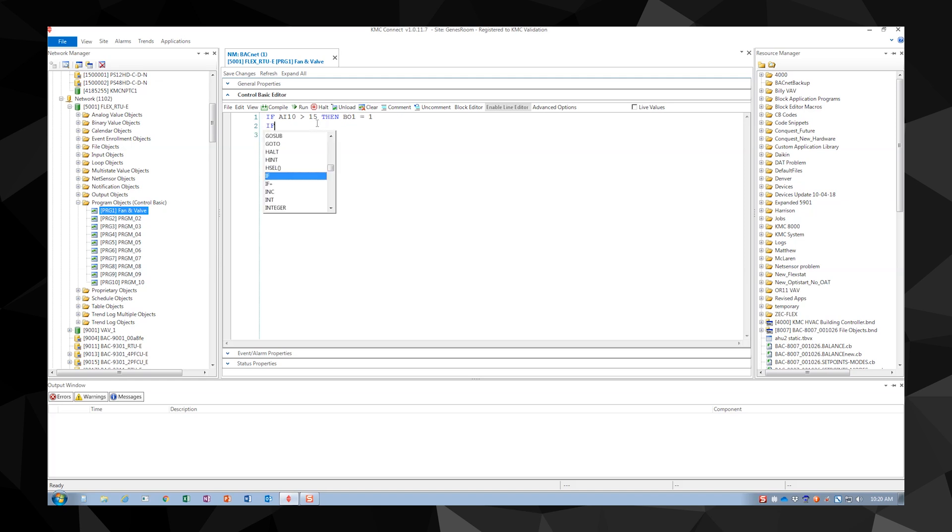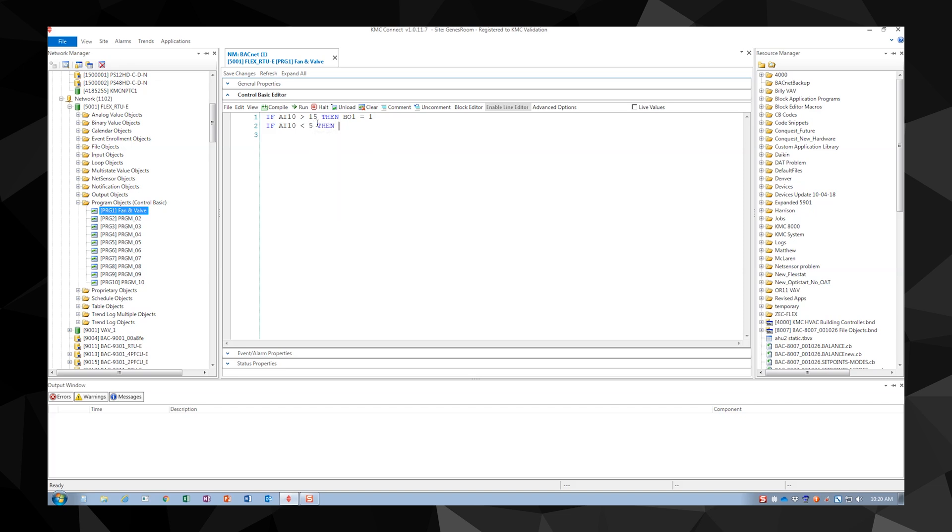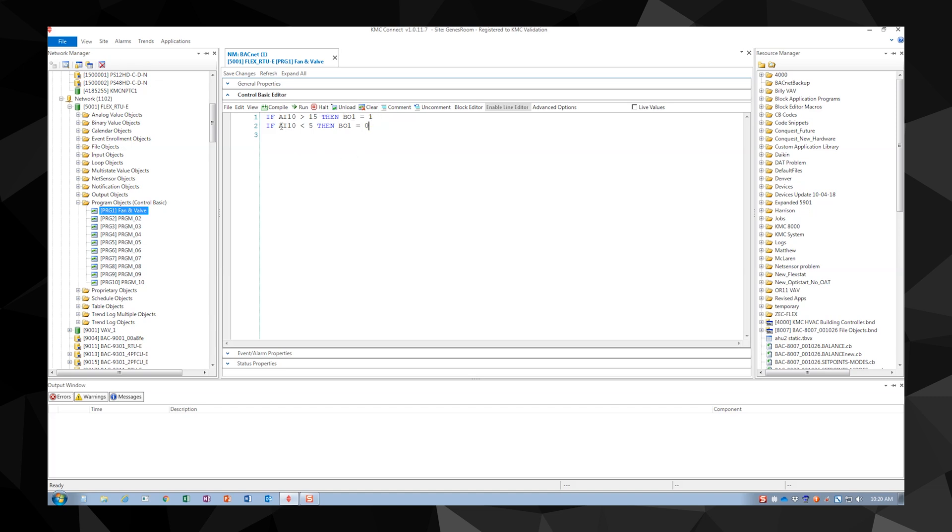Our second line of code will read if analog input 10 is less than 5 then binary output 1 equals 0. These two lines of code work together. If analog input 10 is greater than 15, binary output 1 will be set to 1 or it will be started. Once analog input 10 falls to less than 5, then binary output 1 will be set to 0 or stopped.